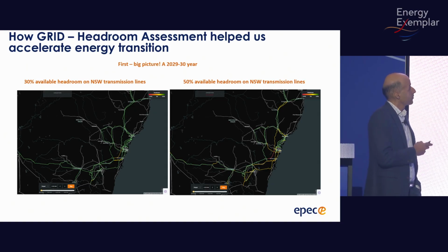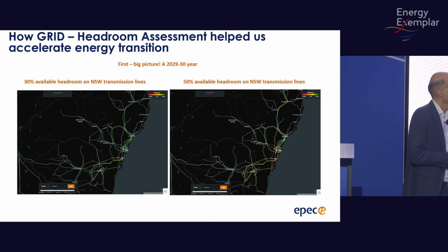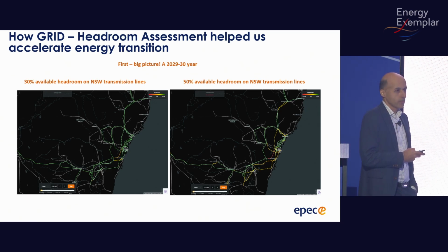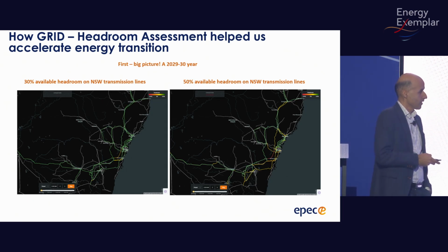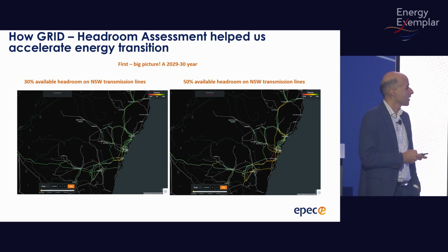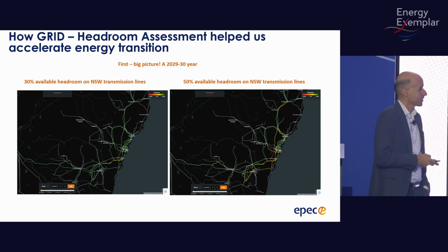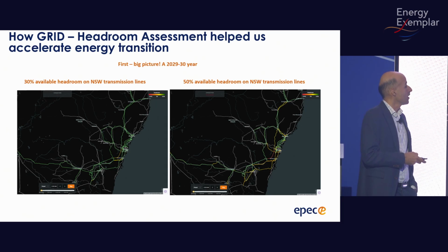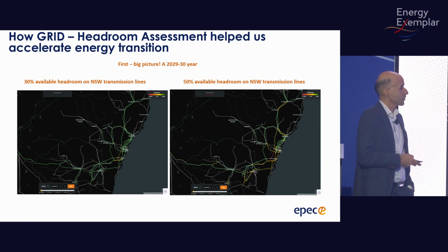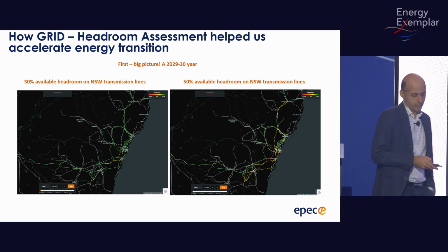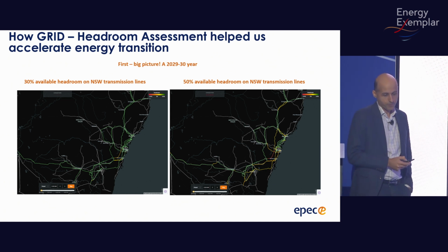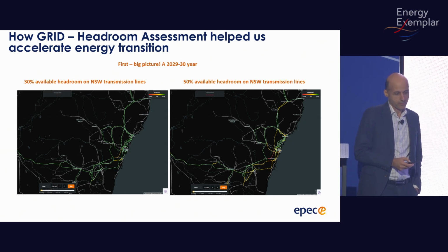If 30% headroom on a 330 kV line is around 300 megawatts, and I push to 50% headroom as a bit of a stress test - line 39, an important line we'll see some news about in the next few months - it starts getting red, along with a bunch of other lines in New South Wales close to the QNI interconnector. All the way south it's yellowish, not much headroom available. That's the different headroom picture.